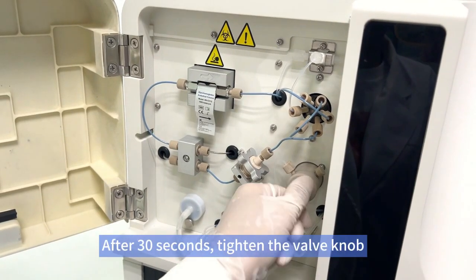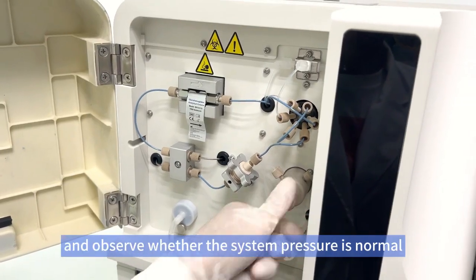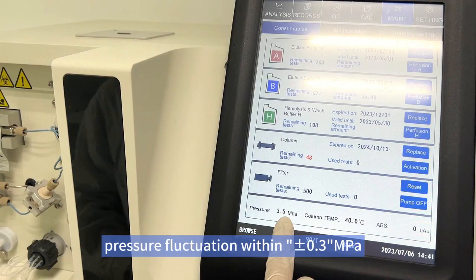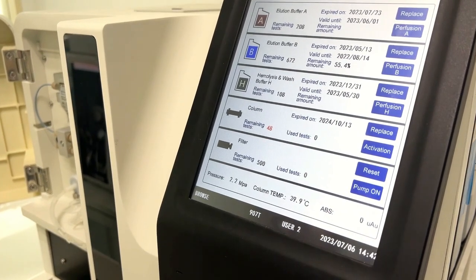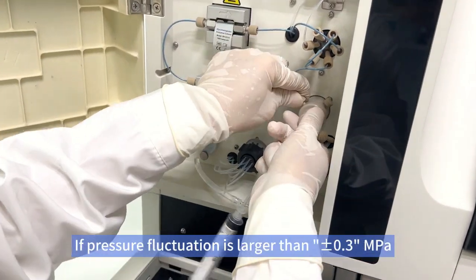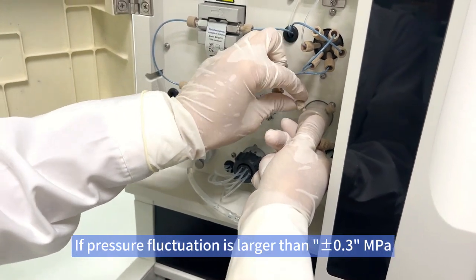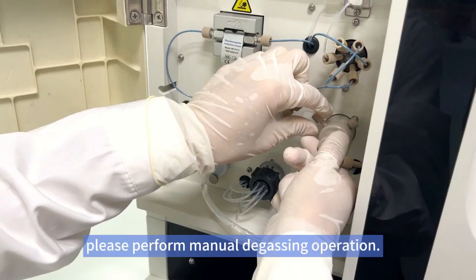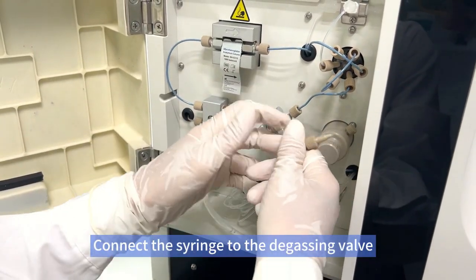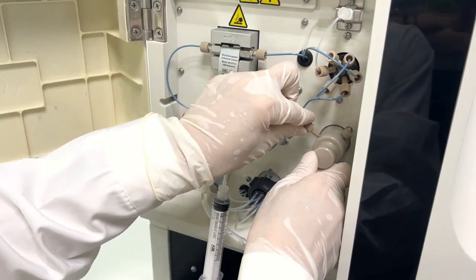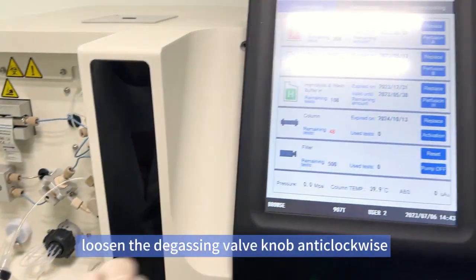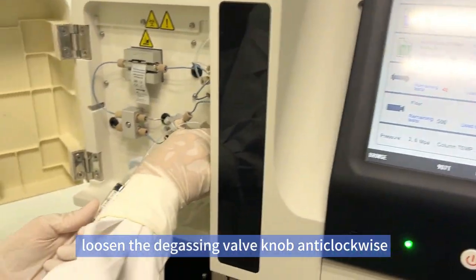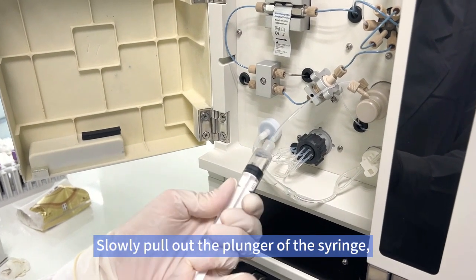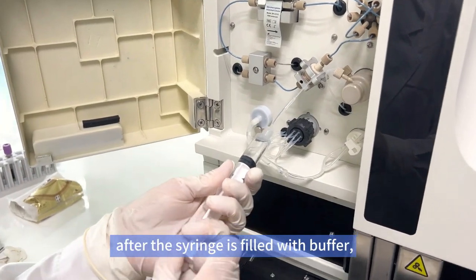After 30 seconds, tighten the valve knob, and observe whether the system pressure is normal, pressure fluctuation within plus or minus 0.3 MPa, otherwise, repeat the above procedure. Click the Pump Off button. If pressure fluctuation is larger than plus or minus 0.3 MPa, please perform manual degassing operation. Connect the syringe to the degassing valve. Click the Pump On button, loosen the degassing valve knob anti-clockwise. Slowly pull out the plunger of the syringe, after the syringe is filled with buffer.